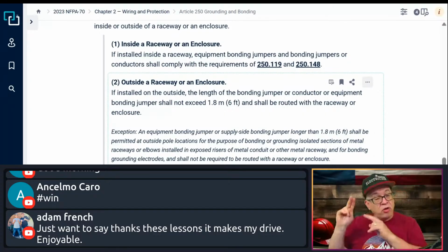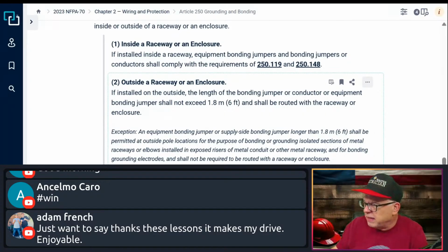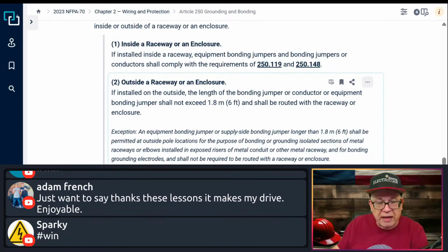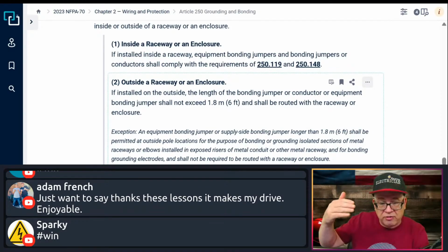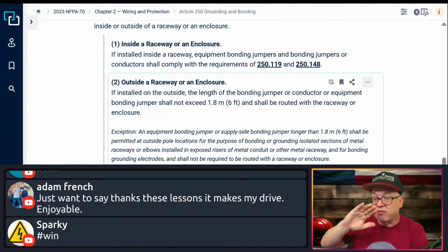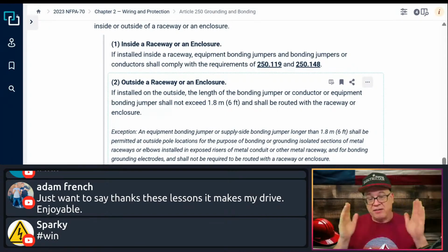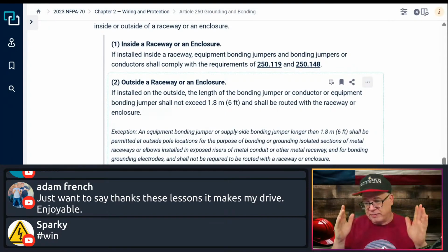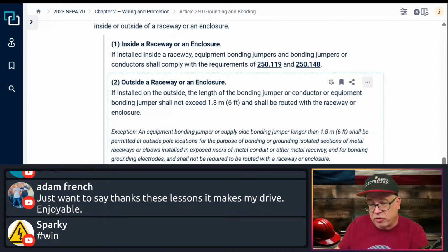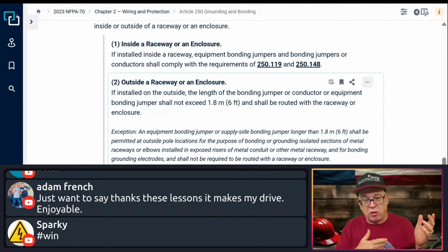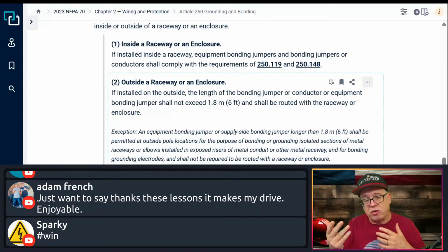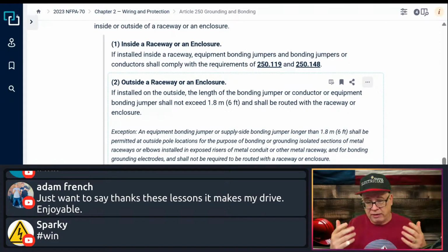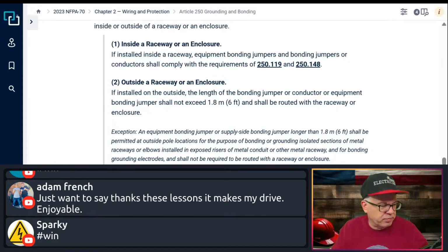For those applications, it will let you be an equipment bonding jumper or supply side jumper a little longer than 6 feet in order to achieve that. Otherwise, the jumper outside is limited to 6 feet. Inside, no limit. Okay. And yes, an equipment grounding conductor also can serve as a bonding function as well. Just make sure it's sized appropriately. And it typically will, because it's all going to send you back to the size of the overcurrent device, and that's how you should be sizing your equipment grounding conductor anyway, right? Makes sense? Get back to the lesson.